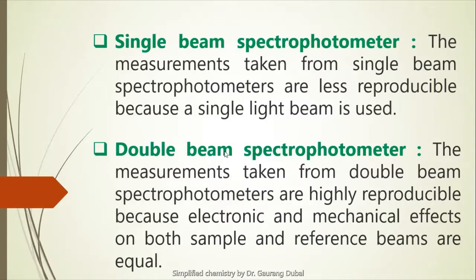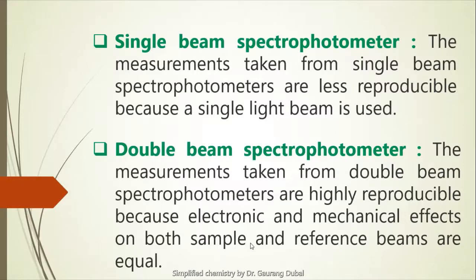The last difference between single beam and double beam spectrophotometer: the single beam gives less reproducible results, meaning not perfectly consistent, while measurements taken from the double beam spectrophotometer are highly reproducible because electronic and mechanical effects on both the sample and reference beams are equal. Therefore, the double beam spectrophotometer is more precise in comparison to the single beam. These are the key differences — thank you for listening.